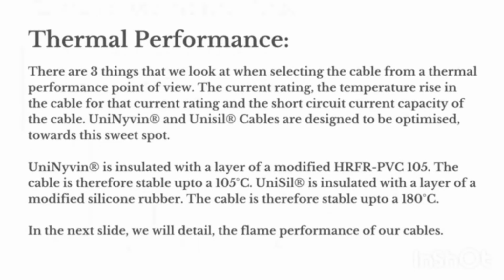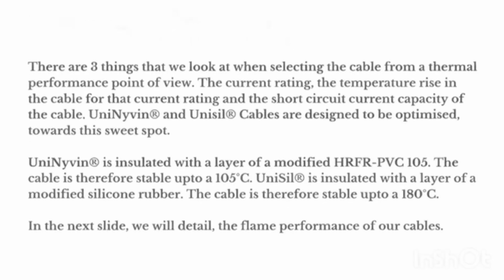Thermal performance. There are 3 things that we look at when selecting a cable from a thermal performance point of view: the current rating, the temperature rise in that cable for that current rating, and the short circuit current carrying capacity of that cable. UniNyvin and Unisil are designed to be optimized towards this sweet spot. UniNyvin is insulated with a layer of modified HRFR PVC. The cable is therefore stable up to 105 degrees. Unisil is insulated with a layer of modified silicone rubber and is therefore stable up to a temperature of 180 degrees Celsius. In the next slide, we will detail the flame performance of our cables.